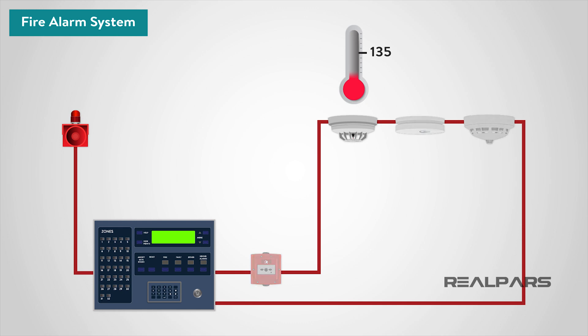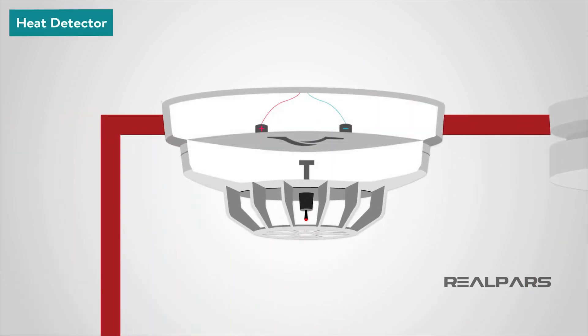A heat detector can either work on a fixed temperature basis where it will trigger an alarm if the temperature exceeds a preset value, or they can work on the rate of change in temperature. Commonly, heat detectors work in a similar way to an electrical fuse. The detectors contain a eutectic alloy which is heat sensitive. When a certain temperature is reached, the alloy turns from a solid to a liquid, which in turn triggers the alarm.